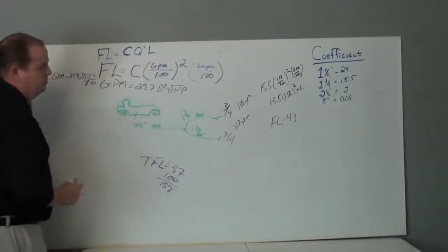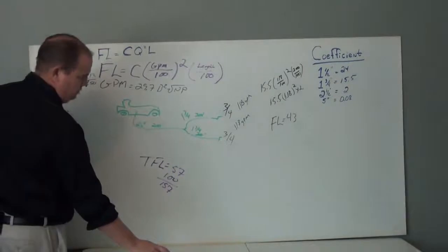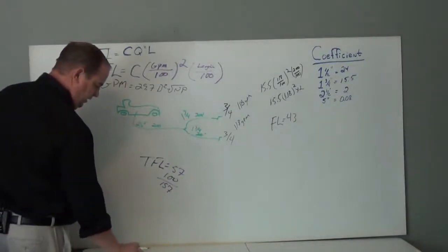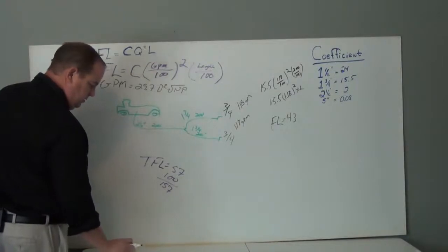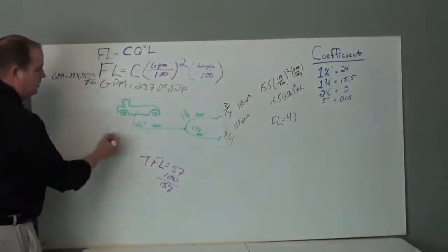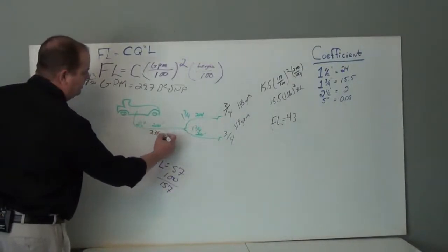So now how much water's flowing through this 2.5? Well, we're supplying two 1 3/4s, so we've got to add these together. So that's what? 236. Punch in the calculator, make sure that's right. 118, 236. So I'm flowing 236 gallons per minute.